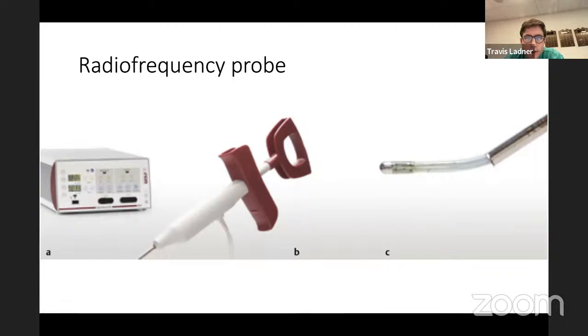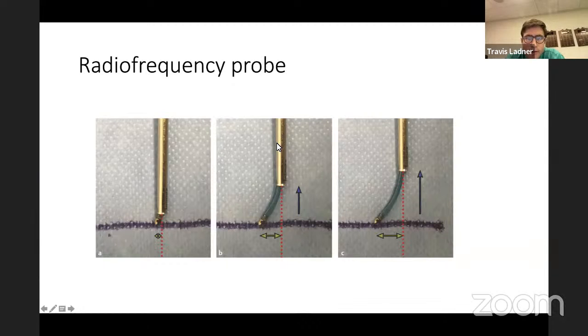An innovation that's really helped with these operations is the development of a radiofrequency probe that has a couple of cool characteristics to it. One is that there's a handle that will extend the tip of this bipolar instrument so that you can both get curve and get access to more difficult to reach areas, but also gives you both length and width of coverage. You can bend it. This is like a flexible tubing. You can bend it and create an angle that you need if the preset one's not working for you. It has a cut feature and a coag feature similar to Dr. Malis's original bipolar.